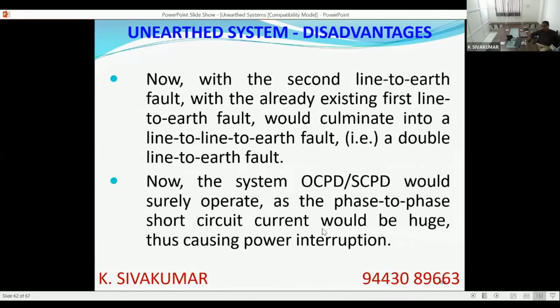Whenever a second earth fault happens, it is no more a line to earth fault, it is a double line to ground fault, as we call it. Now, the system OCPD may not detect a single phase ground fault, as the current is negligible. But when this becomes a line-to-line short circuit, definitely the currents are huge. So definitely the system OCPD or SCPD, overcurrent protective device or short circuit protective device, will operate, as the phase to phase short circuit current is very high, even kiloamperes. So definitely there will be a power interruption.